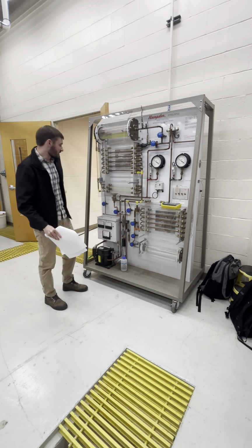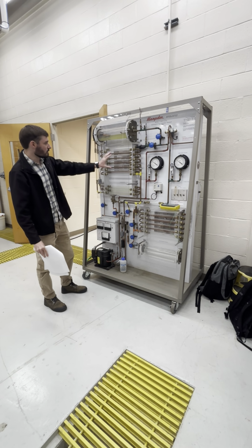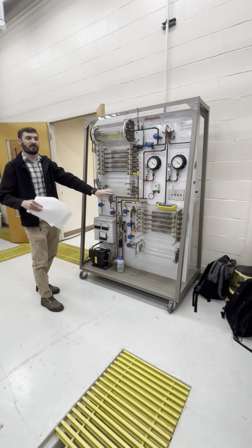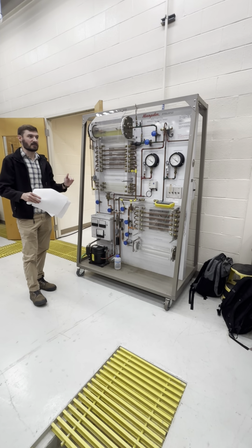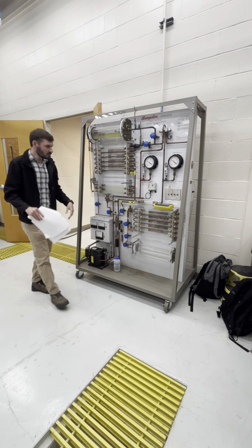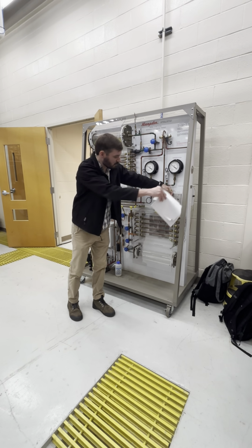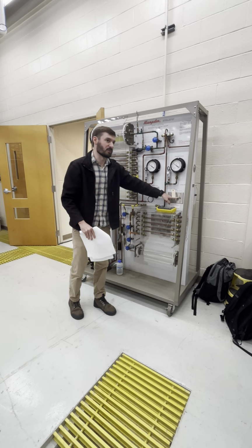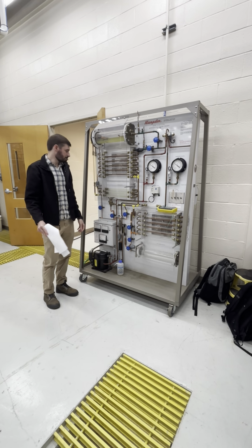Okay? So for the TEV, what we're going to be testing is our two fans. So for one run, we're going to have both the evaporator and the condenser fan on, and then for the other run, we're going to have the evaporator fan off, and we're going to see how that influences the system. Okay? The switches are all located over here. Just make sure it's plugged up in the back. You can flip your fans on, and then when we're ready to start, you can flip your compressor, and then you can go ahead and open up whatever valve you want to start with.